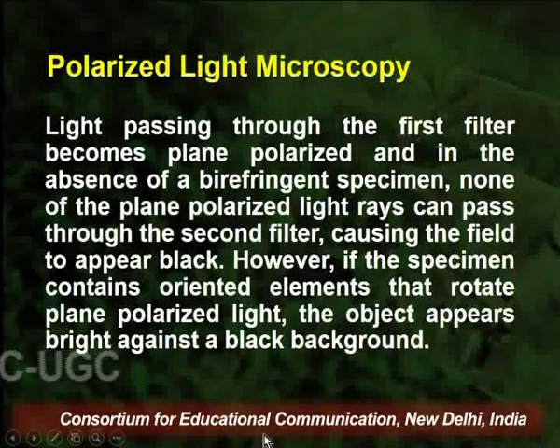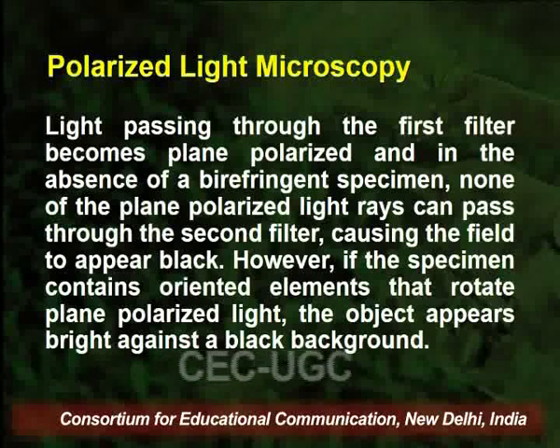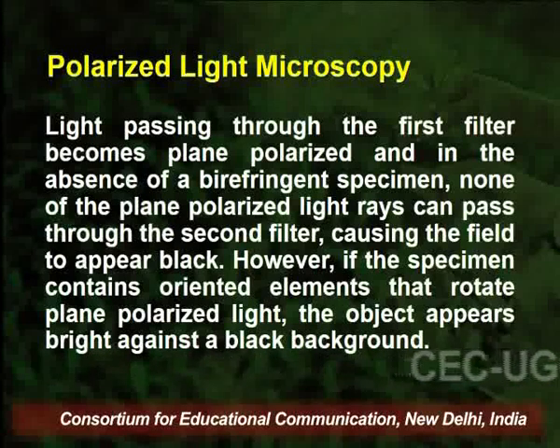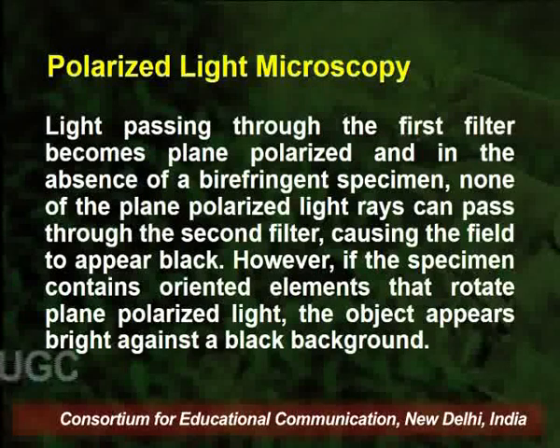Light passing through the first filter becomes plane polarized, and in the absence of a birefringent specimen, none of the plane polarized light rays can pass through the second filter because the second filter is kept at a right angle to the first filter. This causes the field to appear absolutely black. However, if a specimen contains oriented elements that rotate plane polarized light, the object appears bright against a black background.